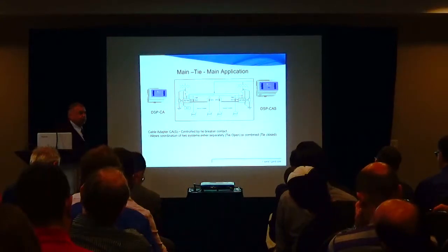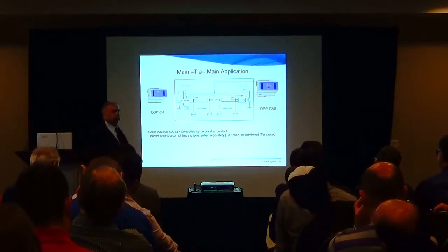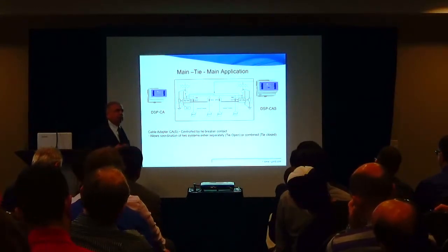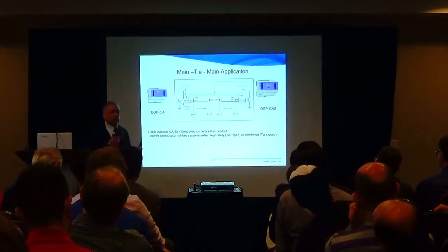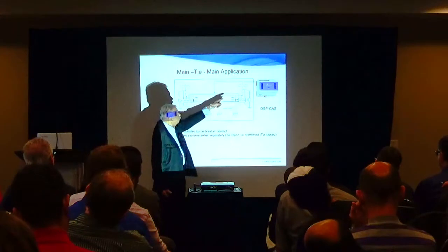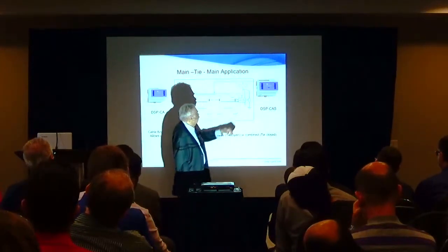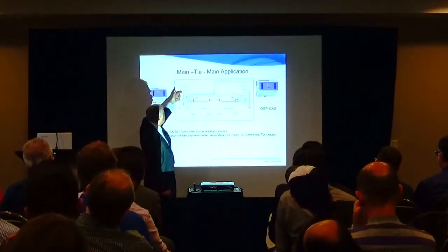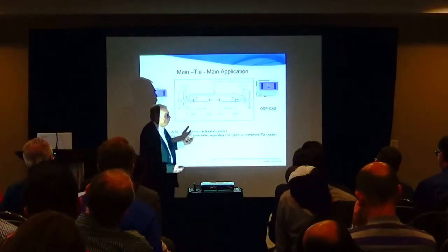In many cases, you have better reliability of operation and more flexibility if you have secondary selective systems. Not only primary selective, but also secondary selective. So you have line one, line two, with two transformers, with a tie breaker. You normally operate with the tie open. You have one main on this side, another main on the other side, and the bus is bifurcated. So now when the tie closes, when you are feeding from one transformer, the other transformer is not available or the main breaker is open, then the one bus requires you to have one system with these two relays connected, so they need to operate as one relay.